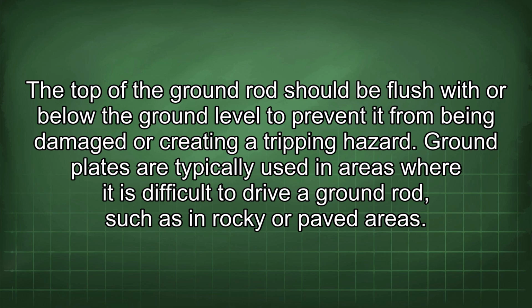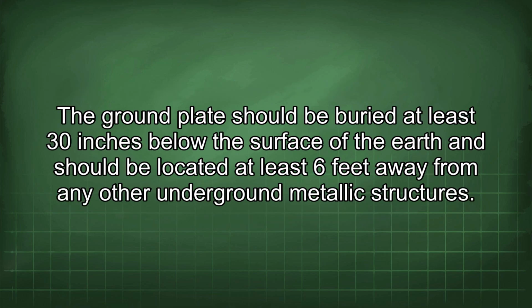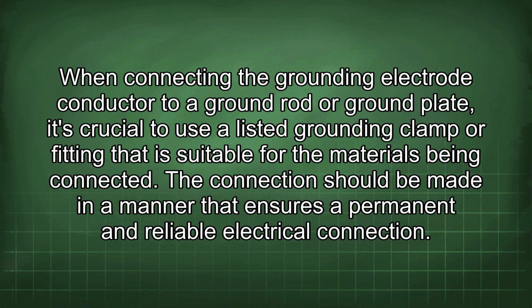Ground plates are typically used in areas where it is difficult to drive a ground rod, such as in rocky or paved areas. The ground plate should be buried at least 30 inches below the surface of the earth and should be located at least 6 feet away from any other underground metallic structures. When connecting the grounding electrode conductor to a ground rod or ground plate, it's crucial to use a listed grounding clamp or fitting that is suitable for the materials being connected. The connection should be made in a manner that ensures a permanent and reliable electrical connection.